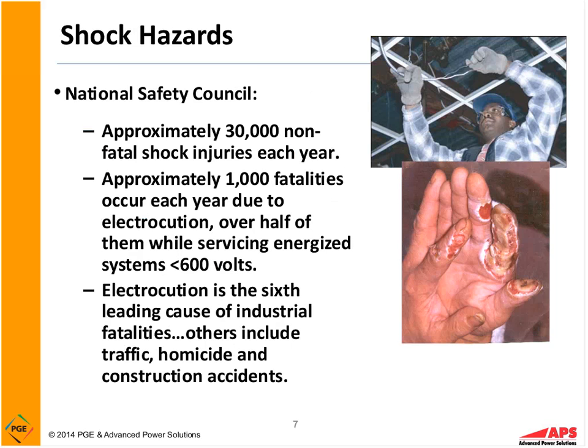So when we look at shock hazards, National Safety Council, approximately 30,000 non-fatal shock injuries each year. 30,000. Approximately 1,000 fatalities each year due to electrocution, with over half of them while servicing energized systems less than 600 volts. So a lot of times people say, well, hey, it's just the big stuff. No, less than 600 volts, over 1,000 fatalities each year. Electrocution, by the way, is the 6th leading cause of industrial fatalities. Still up there at the top, and it still remains one of the top causes of industrial fatalities even after all the implementation of safety measures that we're starting to see in the industry.